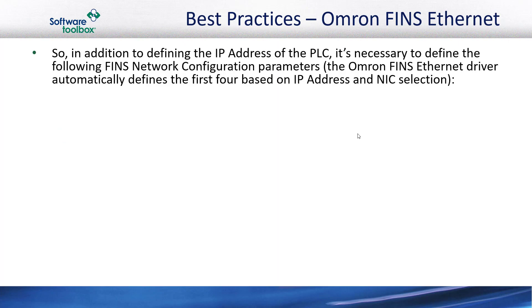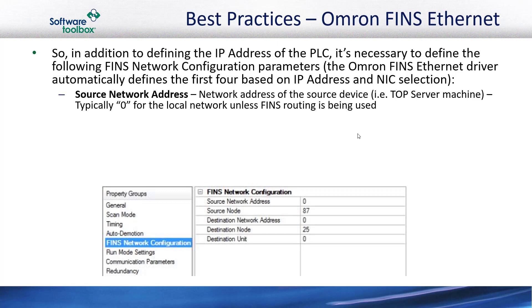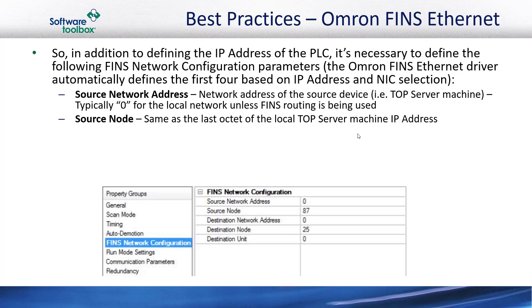Continuing with our best practices, in addition to defining the IP address of the PLC when configuring TopServer, it's necessary to define the following FINS network configuration parameters. The Omron FINS Ethernet driver in TopServer automatically defines the first four based on the IP address and the NIC selected in the configuration. The first FINS network configuration parameter is the source network address — that's the network address of the source device, which in our case is the TopServer machine running the Omron FINS Ethernet driver. Typically zero is used for the local network unless you're using FINS routing to another Omron controller. The source node is the same as the last octet of the local TopServer machine IP address.